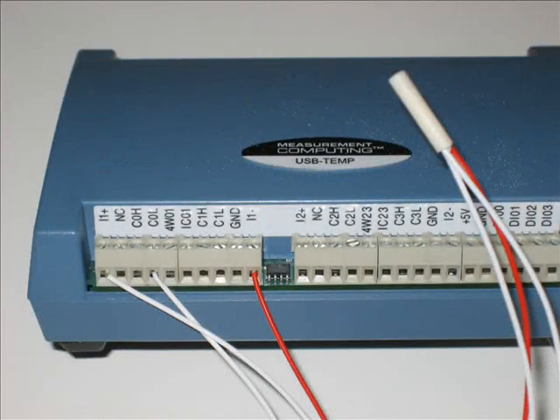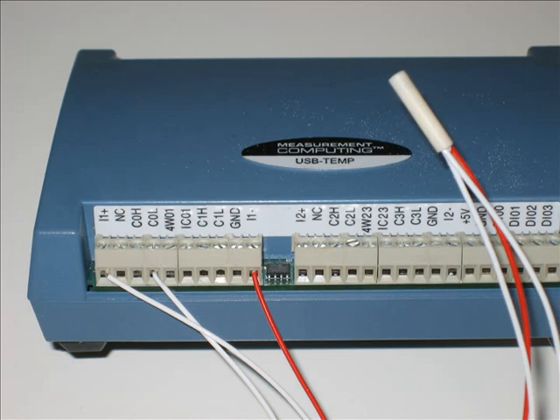An RTD makes measurements by correlating the resistance of the RTD element with temperature. It requires an excitation current to produce a voltage drop that can be measured differentially across the sensor. The USB temp features four built-in current excitation sources for measuring resistive type sensors.